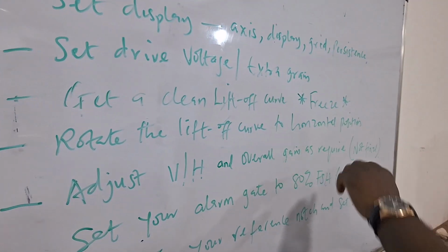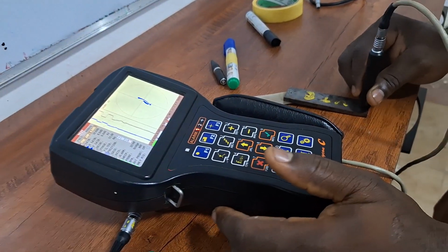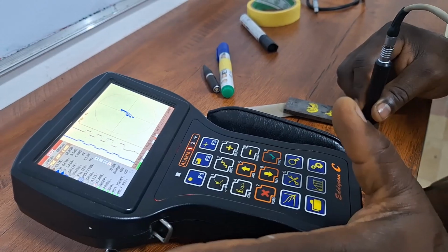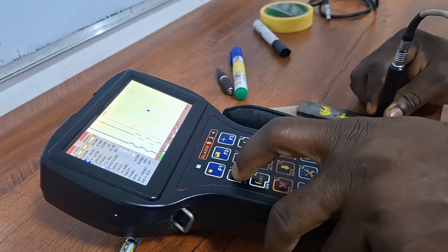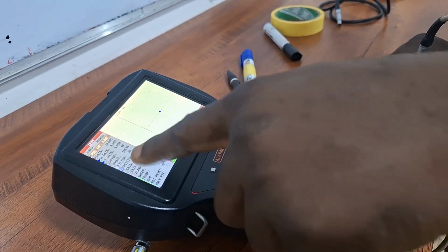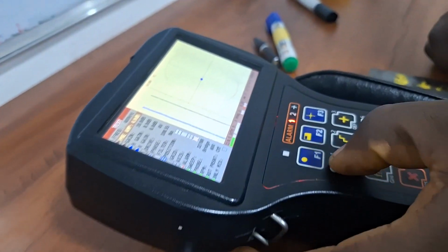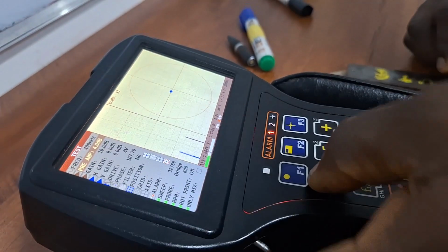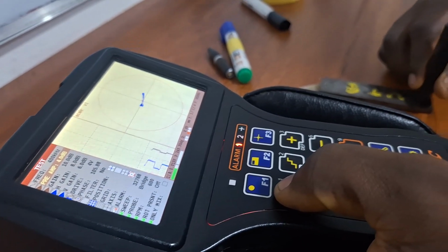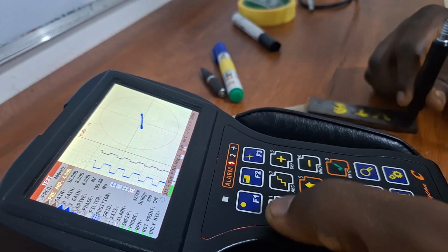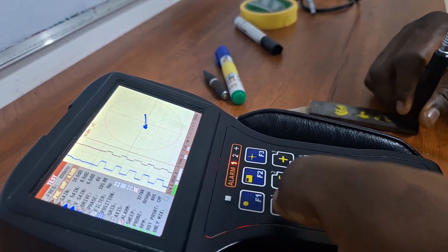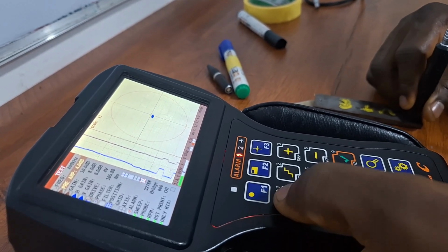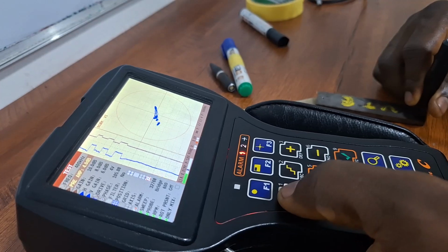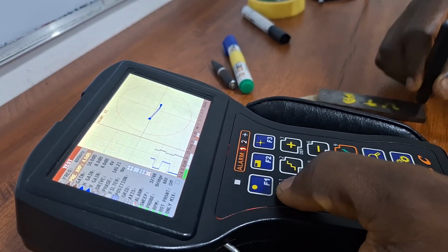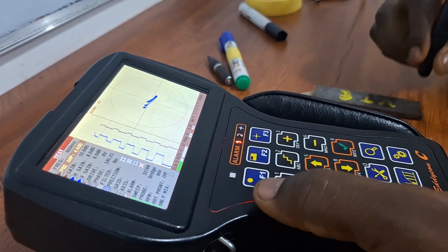So the next thing we do is to rotate the lift-off curve to the horizontal position. If we look at the position of the lift-off now, it's not horizontal. There are several ways of doing it. You can keep pressing on this angle button. If you press the angle button, it changes from about 50 something to 108 degrees. If I press again, it changes to 107. If you want to automatically set your lift-off curve to the horizontal position, that is what this button does. So this button automatically tries to set the angle of your lift-off curve to the horizontal position. You see, it's trying to set it to the horizontal position.